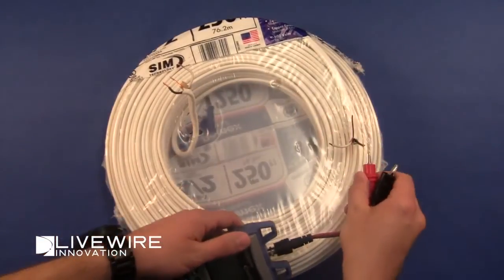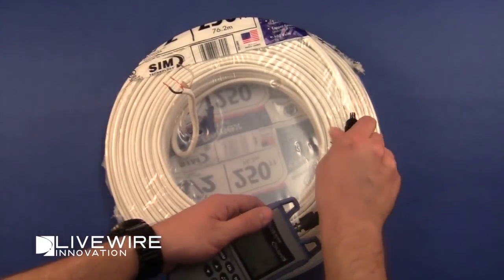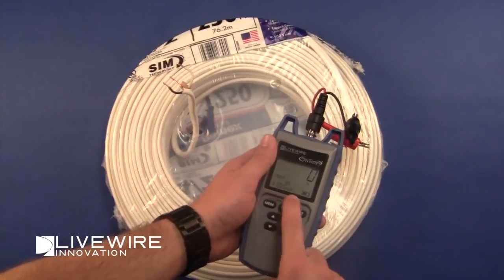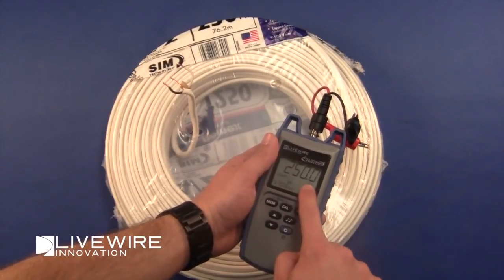We're going to detect the length of this 14/2 Romex. We attach the Fault Chaser to the cable and have already selected the known NVP value of 70.6. It tells us that the length of this cable is 250 feet.